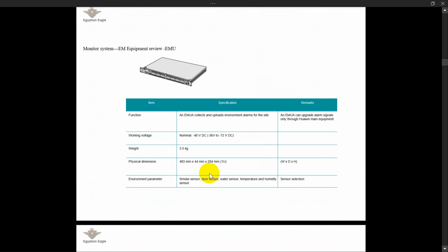We also fix the environmental alarm equipment in the same cabin. For environmental alarm configuration we use the EMU. For monitoring, we fix all external alarms on the EMU, and one of them goes directly to the BBU. Here is the specification for the EMU. The working voltage is minus 48, connected to the rectifier. The weight is 3.5 kg, and the dimensions are width 483 mm, depth 44, and height 284 mm.